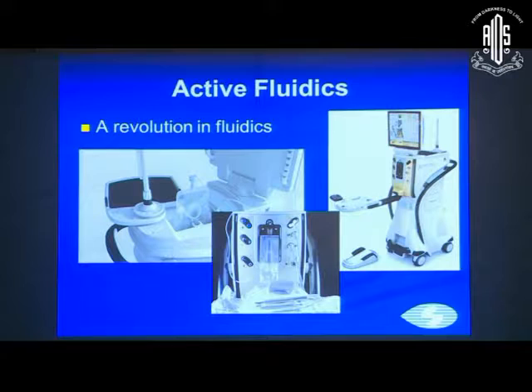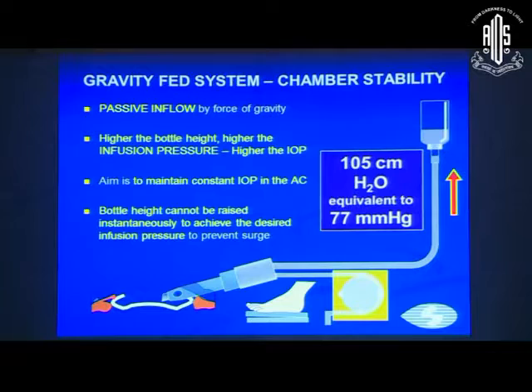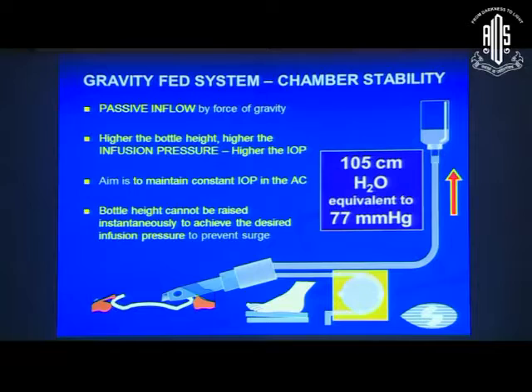A revolution in fluidics called active fluidics is present in the new Centurion machine from Alcon. In gravity-based systems, there is passive inflow by force of gravity — higher bottle height means higher infusion pressure and higher intraocular pressure. The aim is to maintain constant IOP in the anterior chamber; however, bottle height cannot be raised instantaneously to achieve the desired infusion pressure, leading to surge.